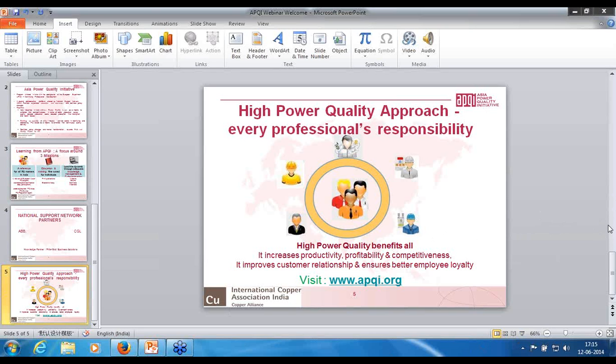So there are devices available. As I said, there is a STATCOM based system or active filter based system which is available in today's market in various forms, and various organizations are supplying that. This can be connected at the transformer output, which will balance all the loads as well as bring down the neutral current, and thereby the neutral to earth voltage.